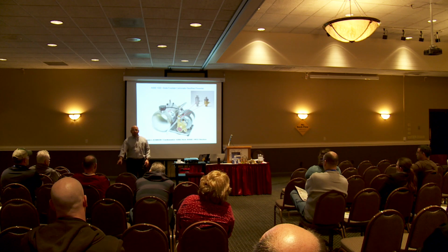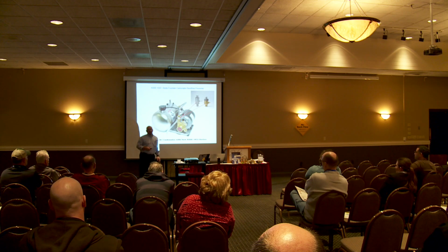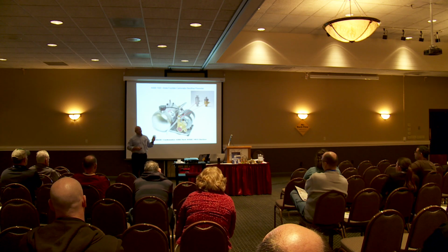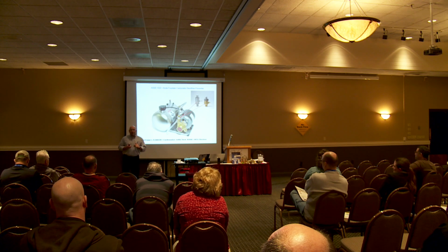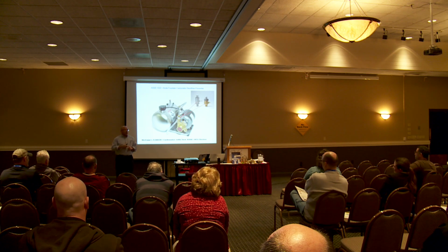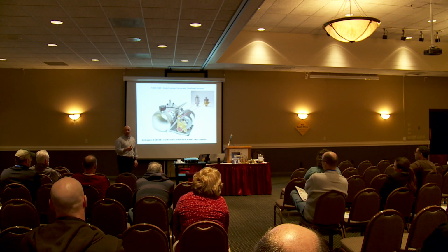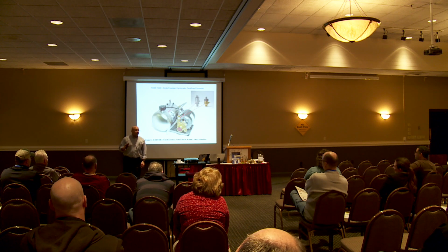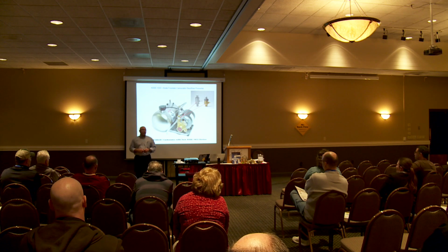Now where's all that water going? We got a puddle, right? So what do we do with puddles or leaks? Plug them. So it's not the system itself, it's when someone modifies this, and we see this often because that flexible hose gets bumped, creates a puddle. And Mr. Manager, we've seen vice grips on it, pinched over duct tape, the port here, a screw threaded right into it to plug it to fix the leak. So now what we have is a backflow preventer with no relief valve, and eventually it ends up failing.